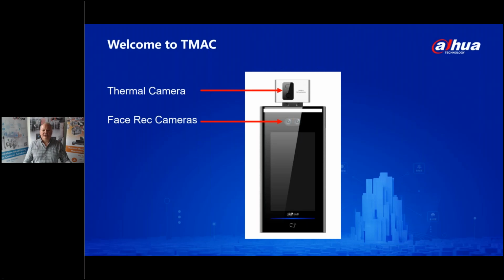That's where our images are. So at the top, I already mentioned the camera system, and then below that there are a couple of cameras there for facial recognition. Because it's an access control panel, it can work with facial recognition, and if that's enabled, those cameras are the ones that are used. It also has a touchscreen display and an RFID card reader. We'll come on to touch on those points a little bit later. But that's what you see externally as a user.